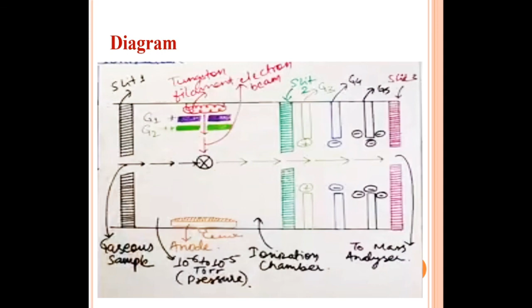which starts from slit 2 and ends at slit 3, named the ion acceleration chamber. In the ion acceleration chamber, again there are 3 electrodes or grids, denoted G3, G4 and G5. The first has positive potential, the second grid shows negative potential and the third grid shows more negative potential. When the ions enter the ion acceleration chamber, the positive ions are deflected by the positive potential electrode and attracted towards the negative potential electrode. Because of this they get some acceleration, tilt towards the right hand side and enter the mass analyzer.